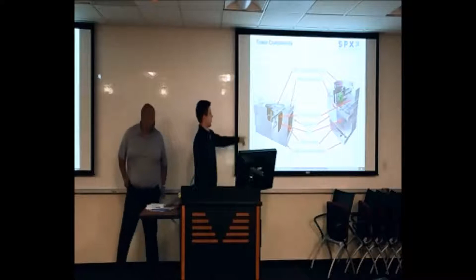One other note on the hot water basins: those should be checked every other month or so. You'll see silt develop around those nozzles, and it can actually plug the nozzles if there's enough buildup.